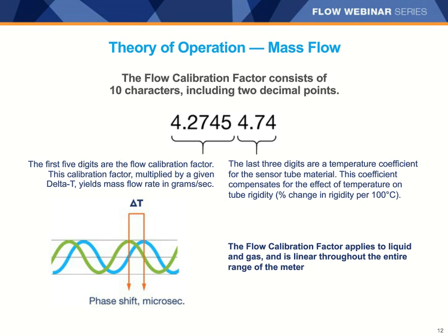could be made. The last 3 digits of the calibration number are a temperature coefficient for the sensor tube material. This coefficient compensates for the effect of temperature on tube rigidity, or Young's modulus of elasticity. It is a percentage change in rigidity per 100 degrees C. The 4.74 number shown here is for stainless steel. A different number would be used for other metallurgies like Hastelloy or titanium. The RTD that measures the tube temperature is plus or minus 1 degree C from the process temperature and can be configured as an output variable as well.